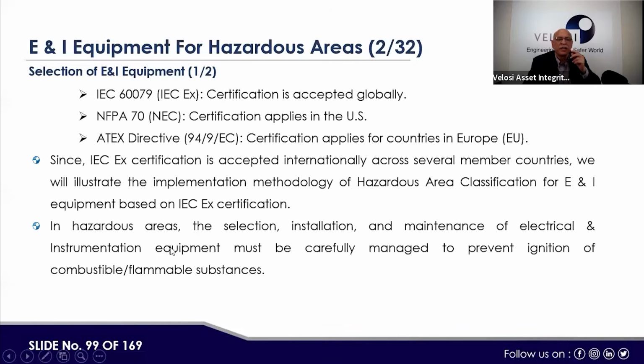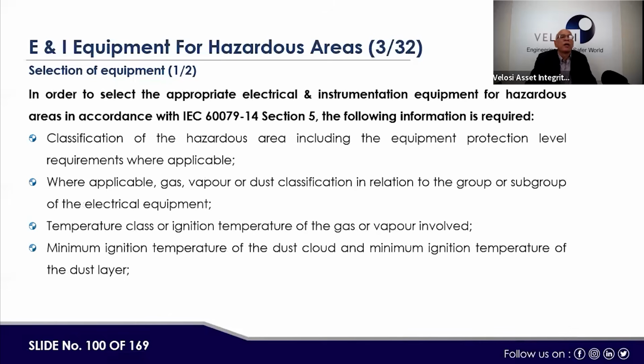In a hazardous area, the selection, installation, and maintenance of electrical and instrumentation equipment must be carefully managed to prevent ignition of combustible, flammable substances in that particular area. In order to select the appropriate electrical and instrumentation equipment for hazardous areas in accordance with IEC 60079, Part 14, Section 5, the following information is generally required. Like we have done hazardous area classification, this slide is asking for the same information.